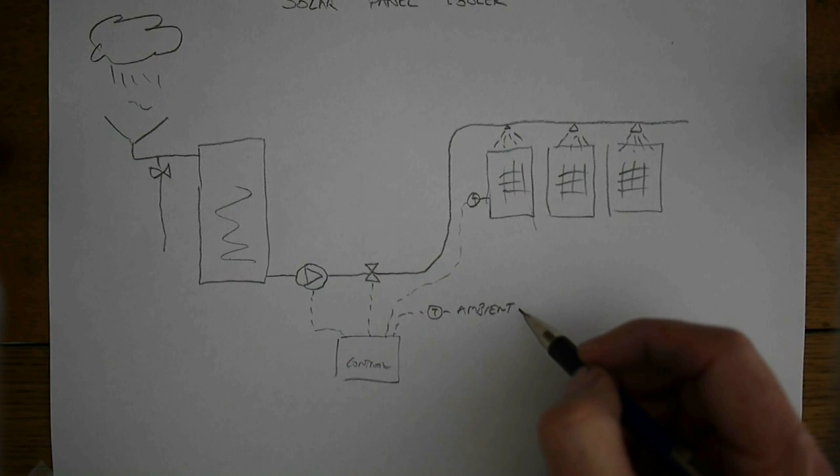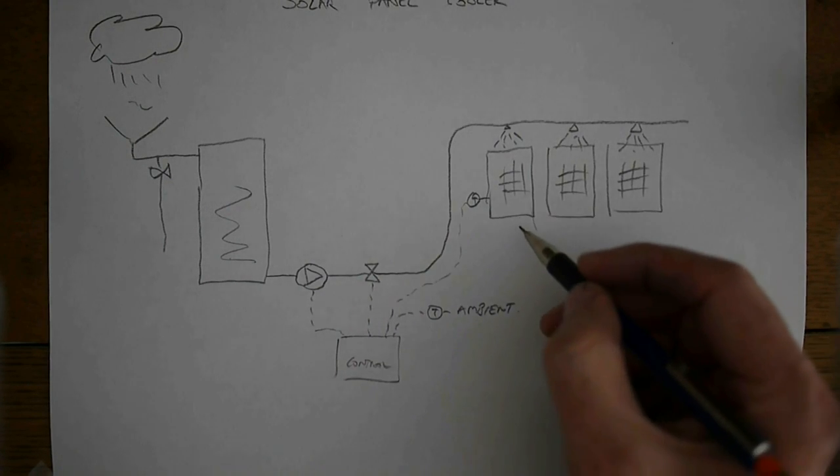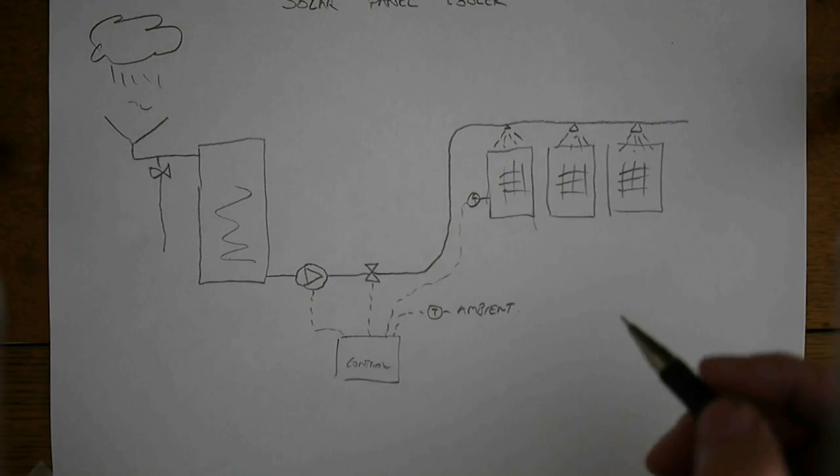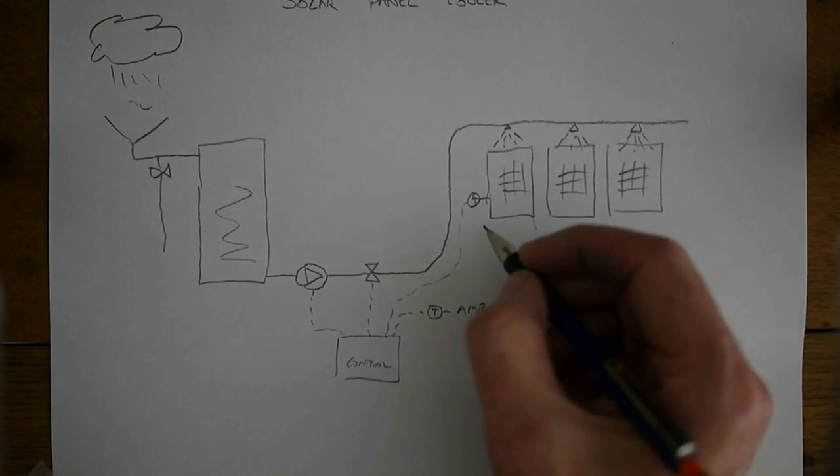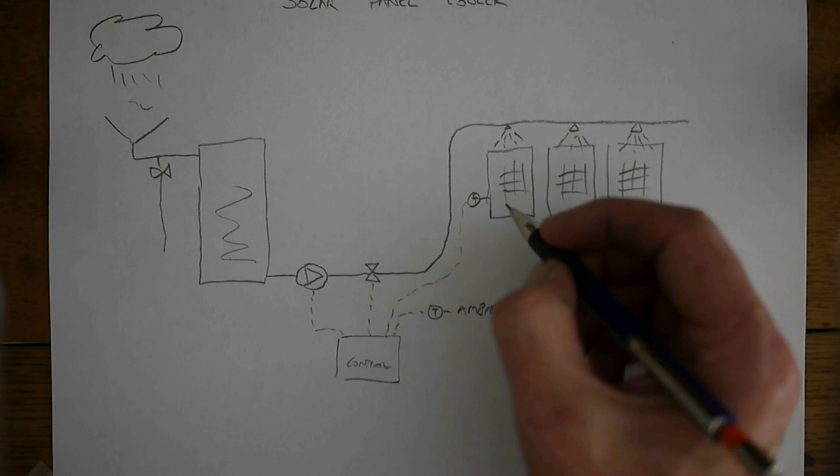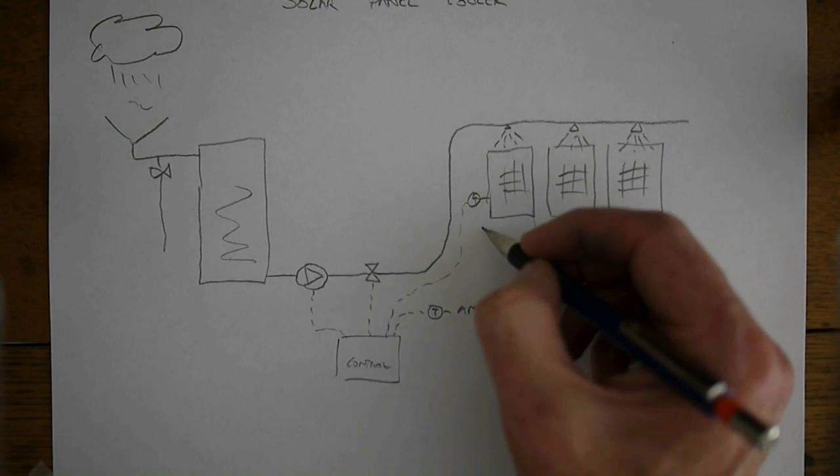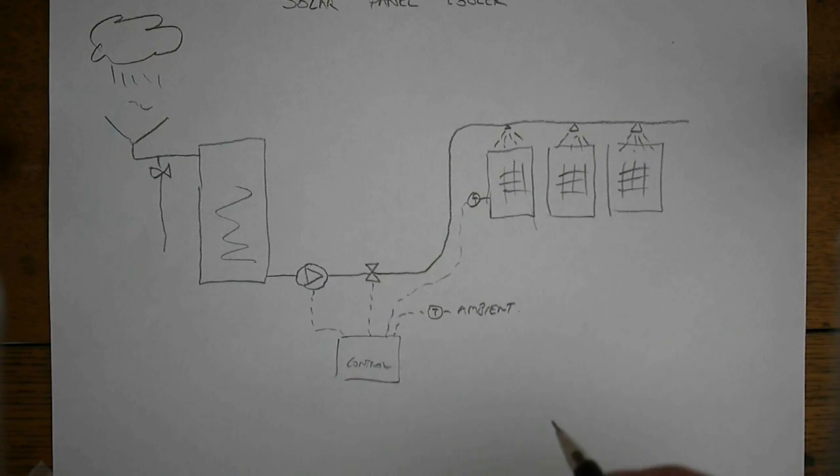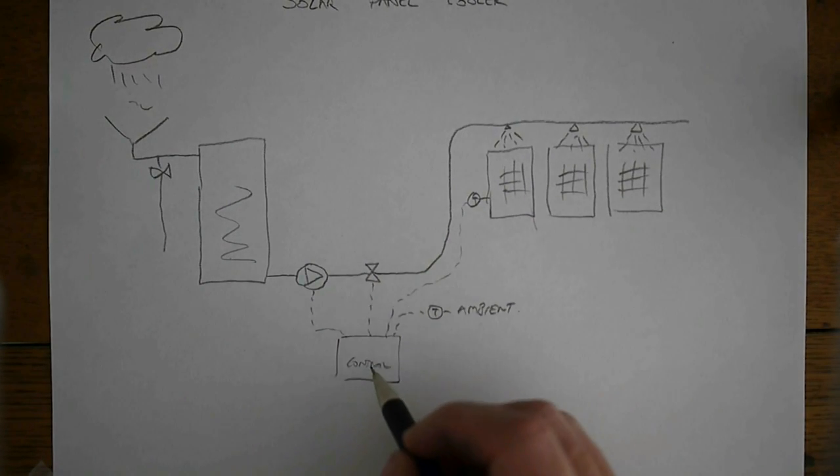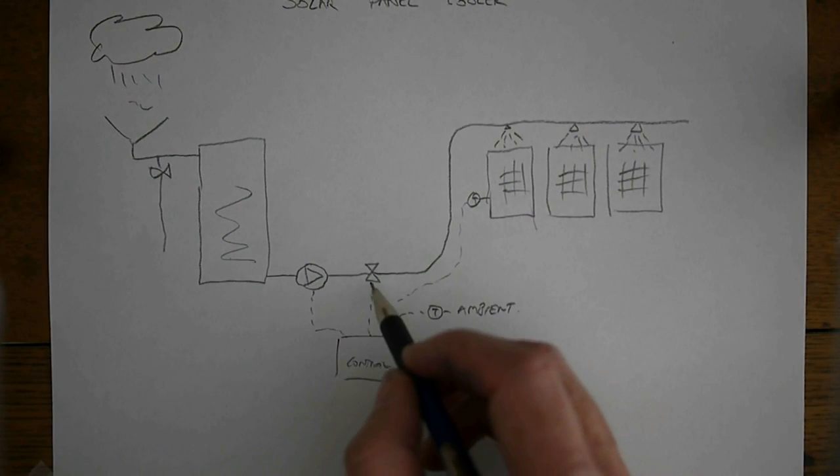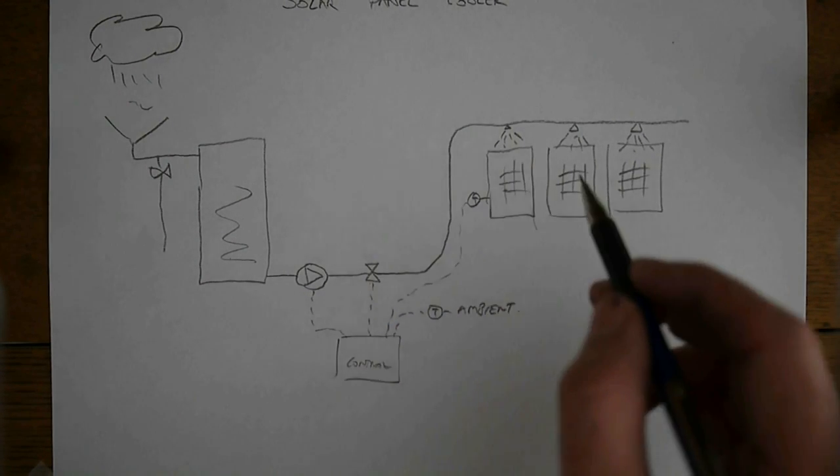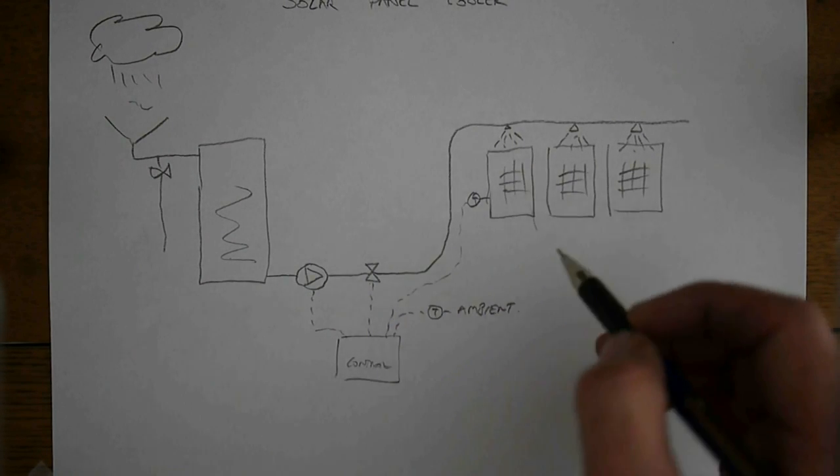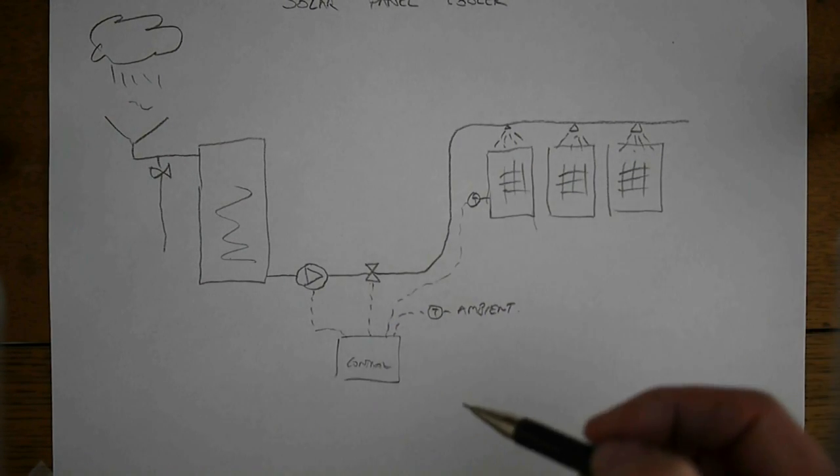When the ambient temperature and the solar panels - when there's a difference of about eight degrees - then the controller starts turning on the valve and turning on the pump to spray some water onto the panels which cools them down.